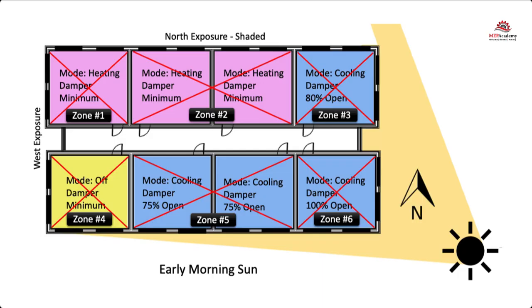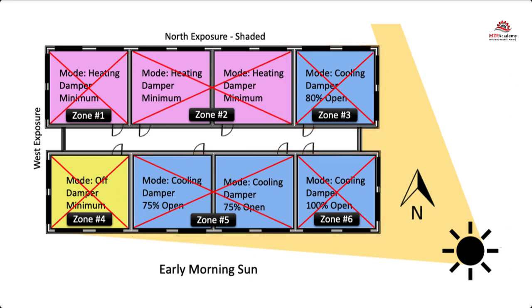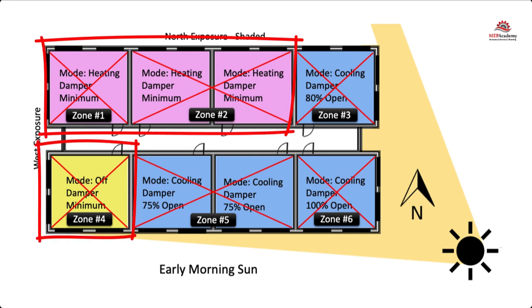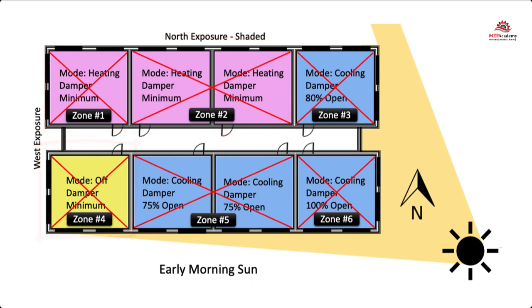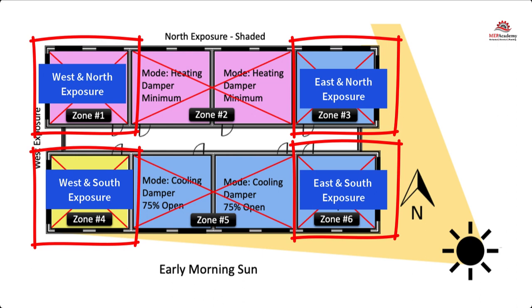Each zone is reacting differently to the early morning sun. Some zones are in cooling mode with their dampers at different percentages of being open, while other zones are in heating, and one zone is off and receiving minimum air for ventilation. This is a very basic diagram of how zones may differ and why it's important to consider how spaces are grouped together, as each space may have a different solar exposure and cooling load profile. Corner spaces are often difficult to include with other spaces because they have two exposures — it's like living on the corner of your block: you have two streets.